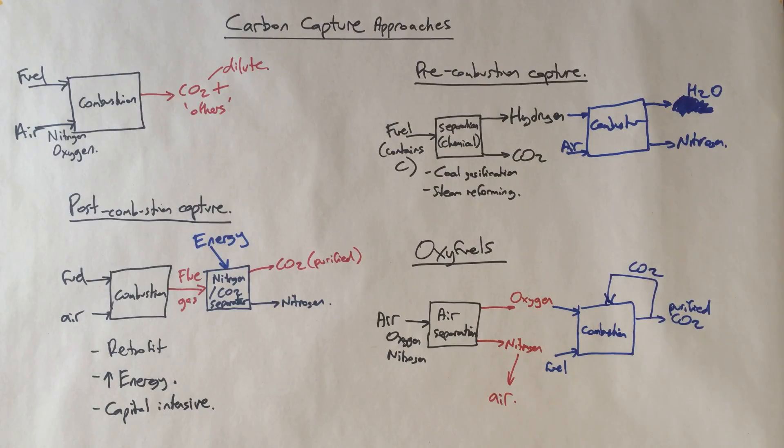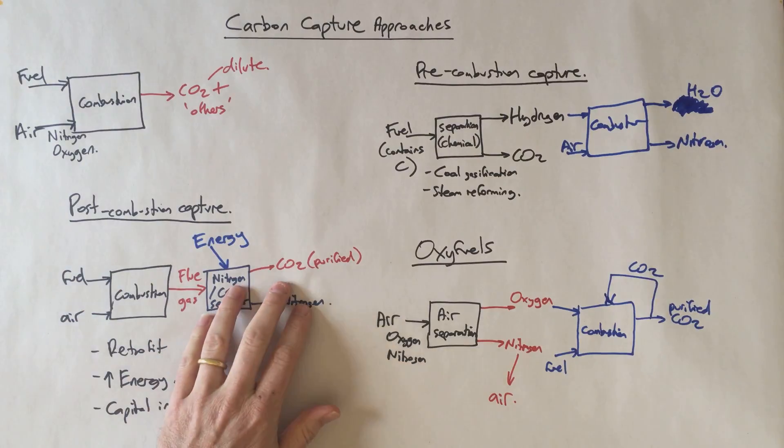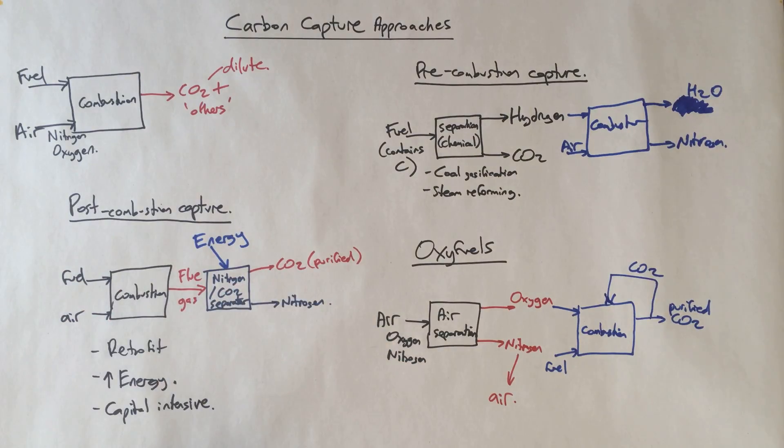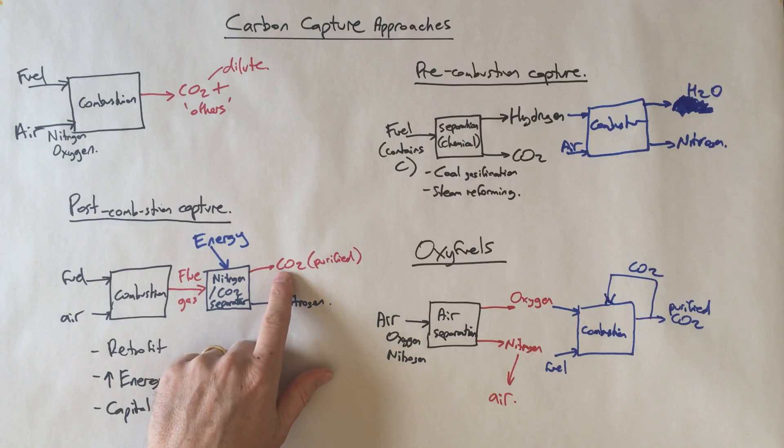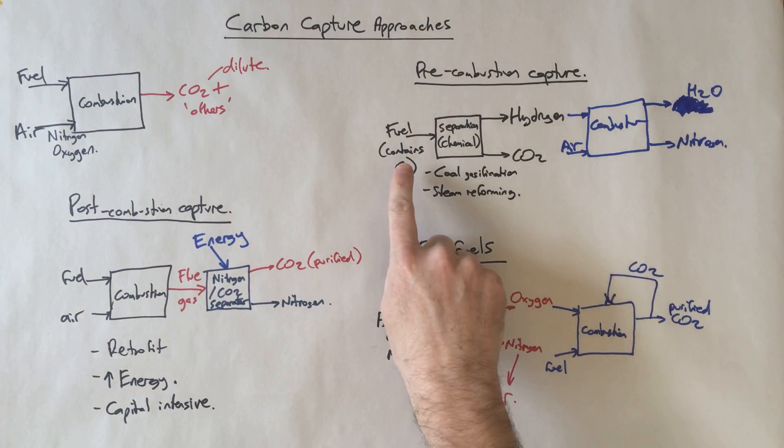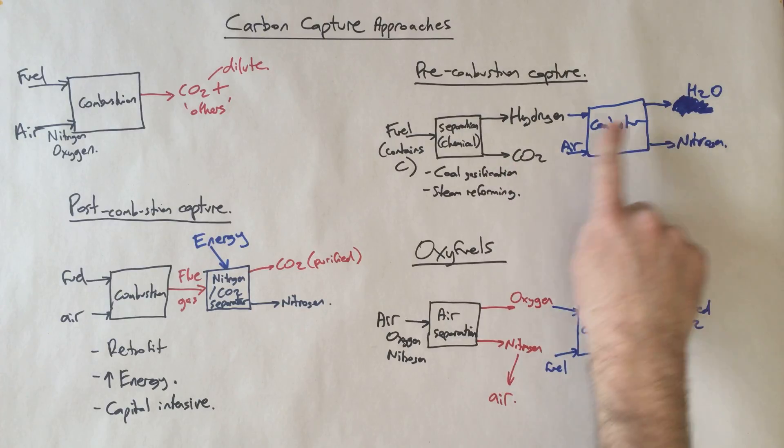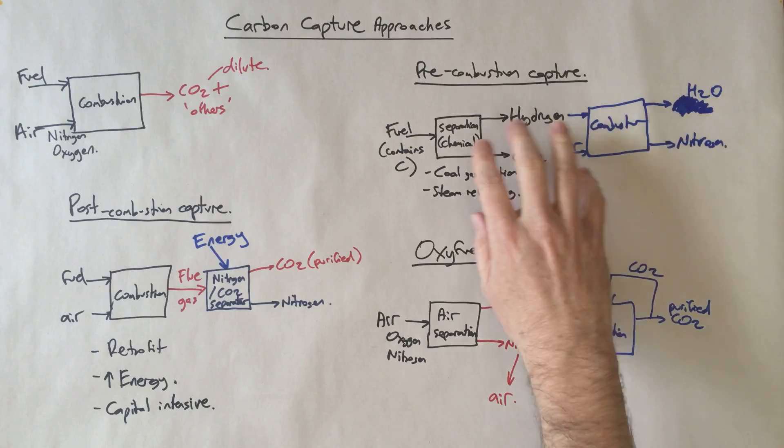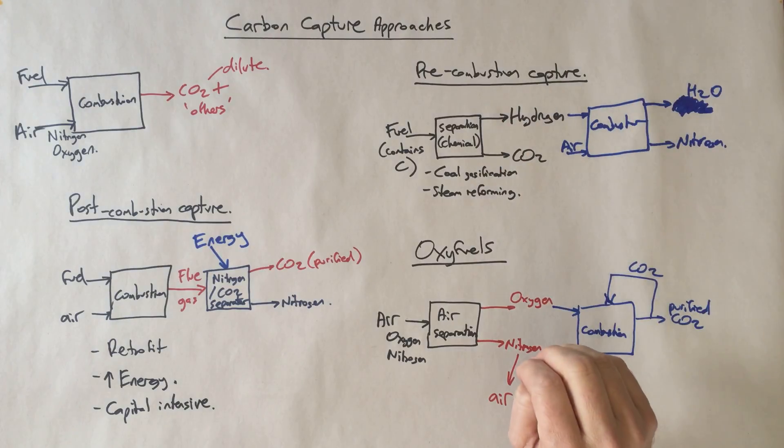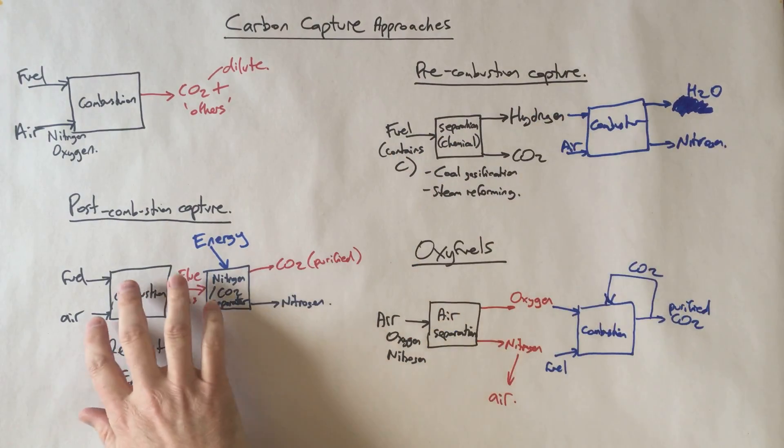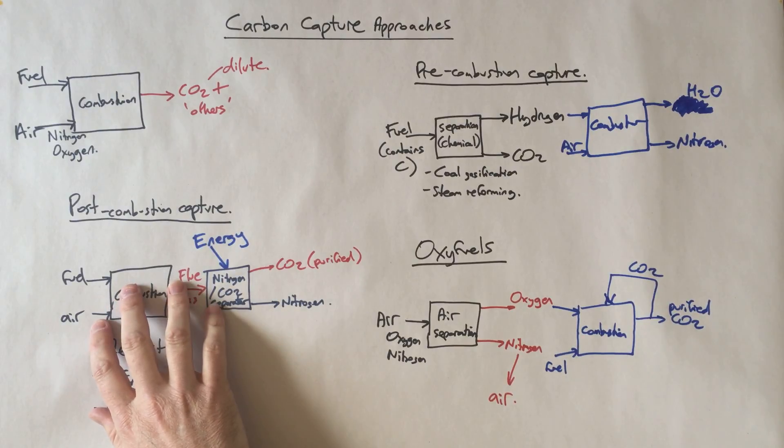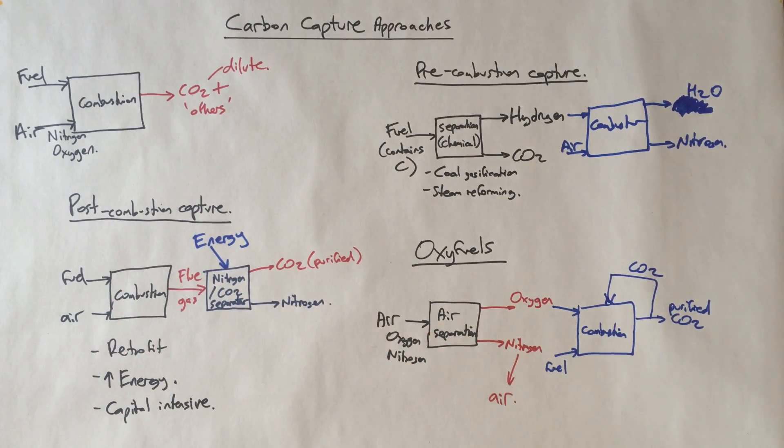So there you have it - there's the three sort of predominant approaches to carbon capture. Post-combustion capture where we can bolt something onto the end of our traditional combustion process and separate out CO2. Pre-combustion capture where we actually treat our fuel to remove carbon from it before we do any combustion - so effectively we're changing everything to a hydrogen combustion plant. As you can appreciate, that's a wholesale change and is not really suitable for retrofit. And finally, we have oxyfuels, which looks at the nitrogen side and removes the nitrogen from the system before we do combustion.